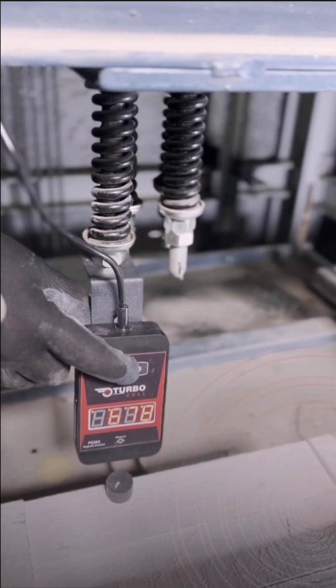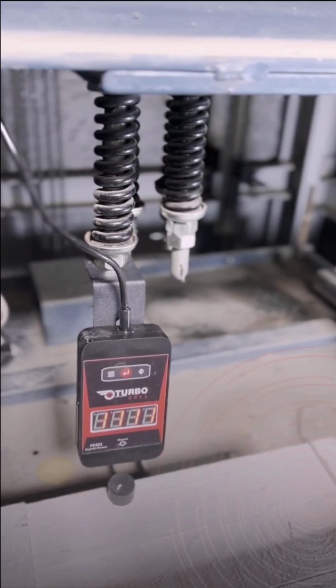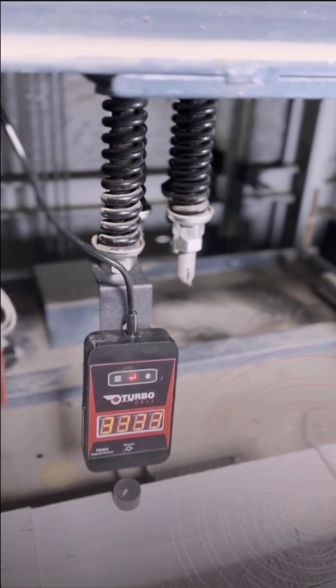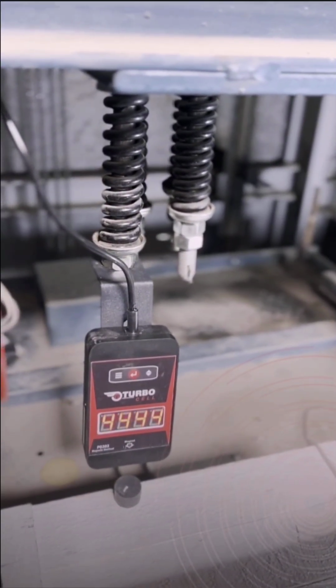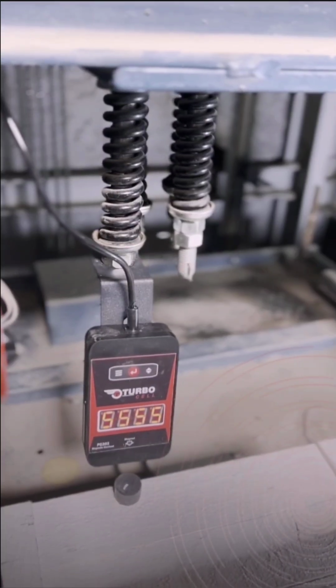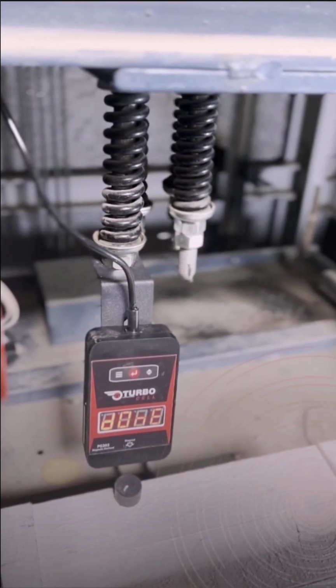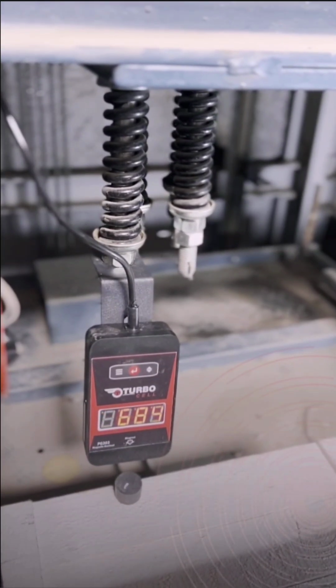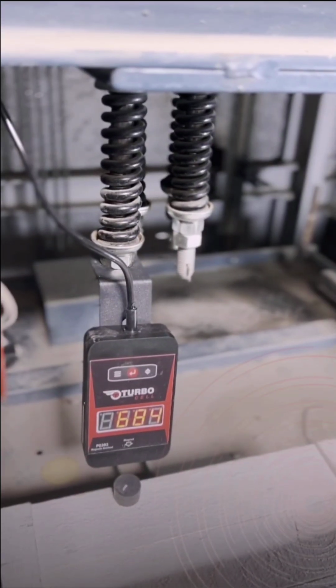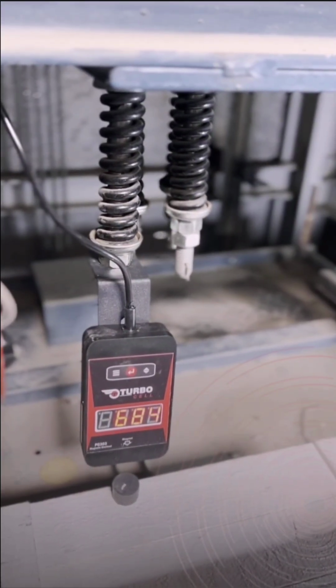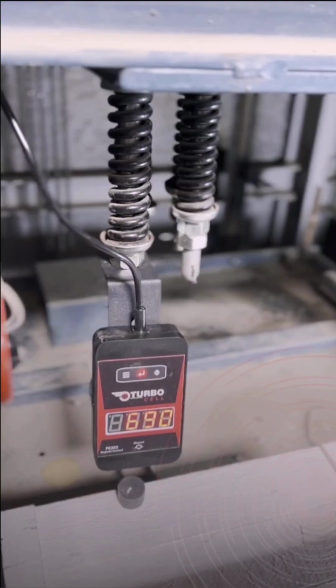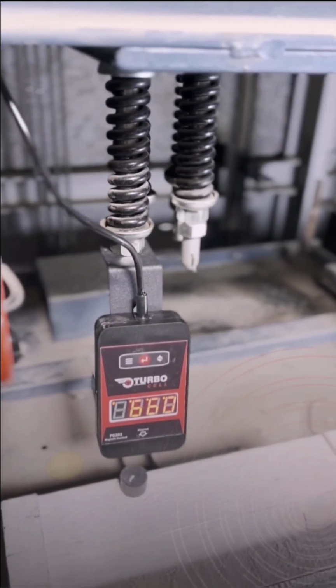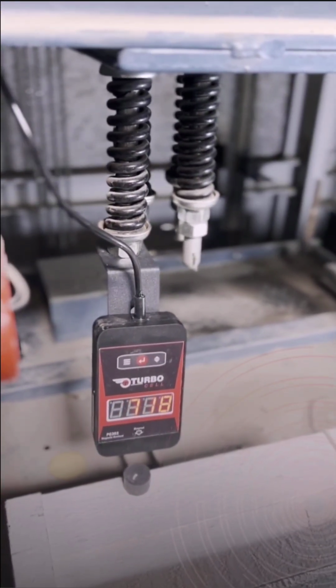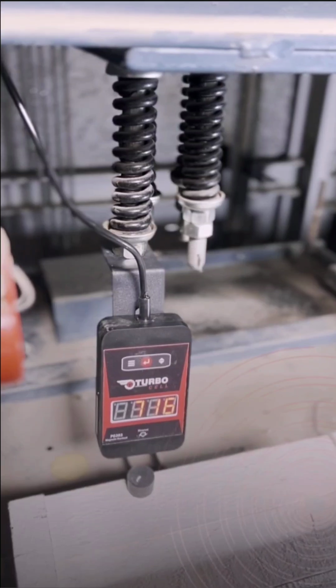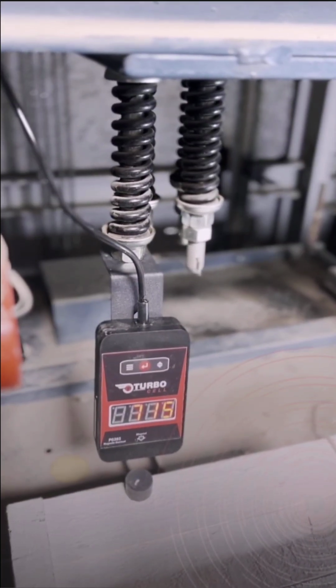Initial calibration. For calibration, first place the full rated load inside the cabin. Once the cabin is fully loaded, press the red button once. The device will then start counting and store the magnetic flux value that matches the cabin load. During an overload, the springs compress, increasing the gap between the sensor and the magnet. In this situation, 4 indicator LEDs on the display will light up, confirming overload detection.